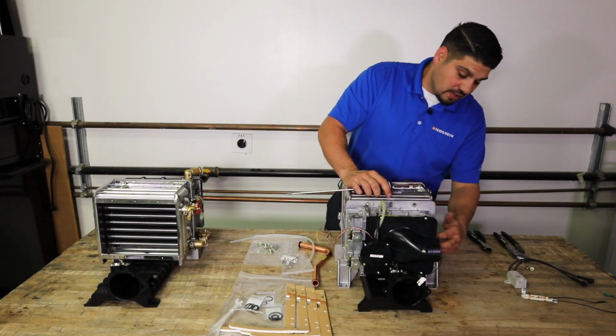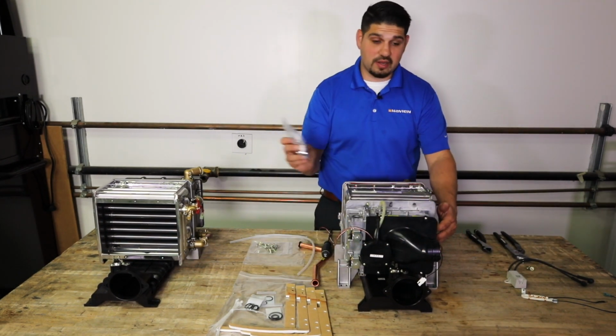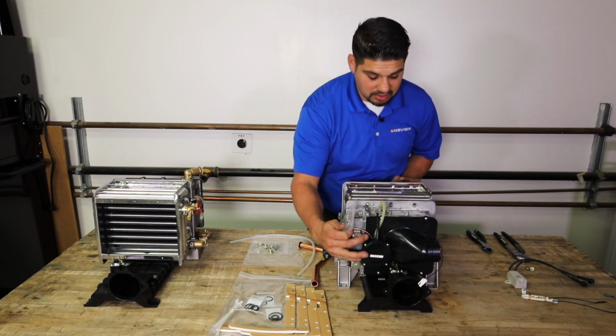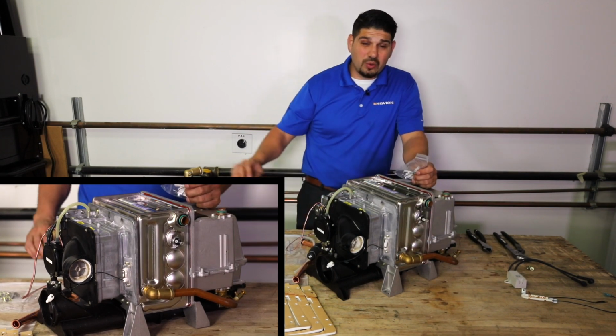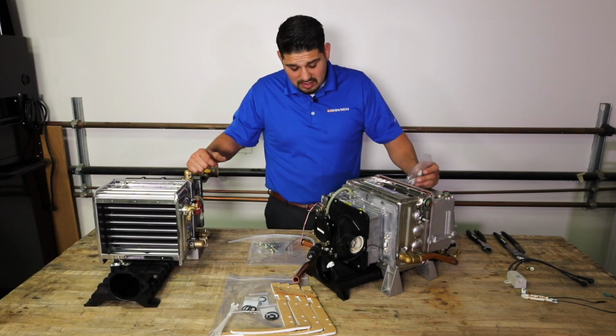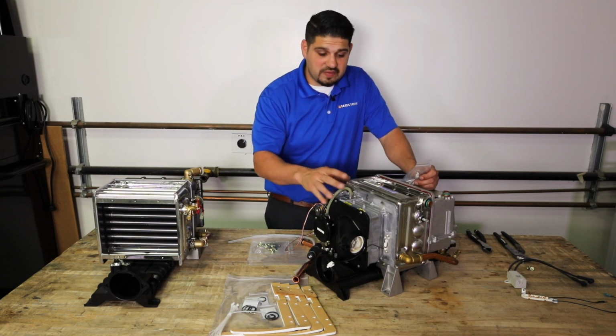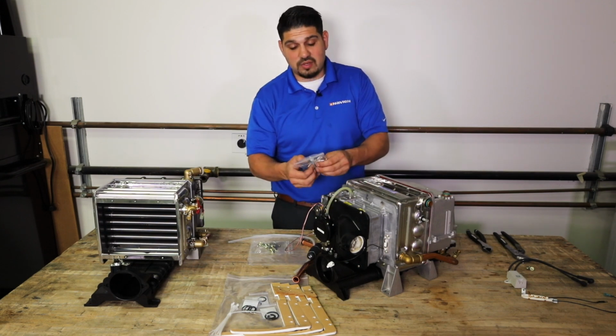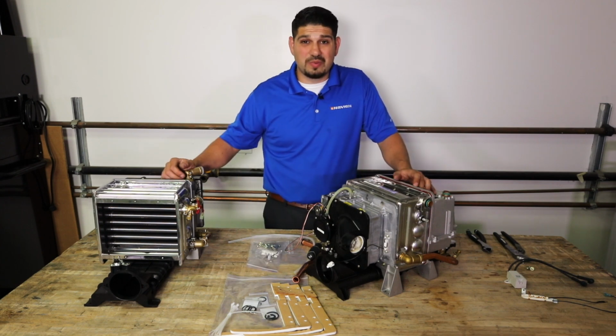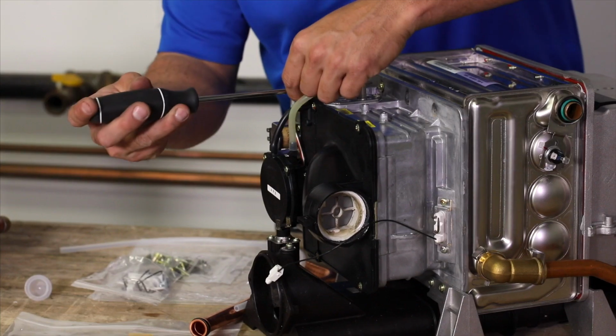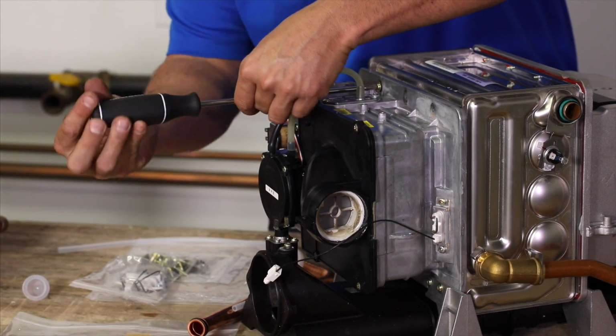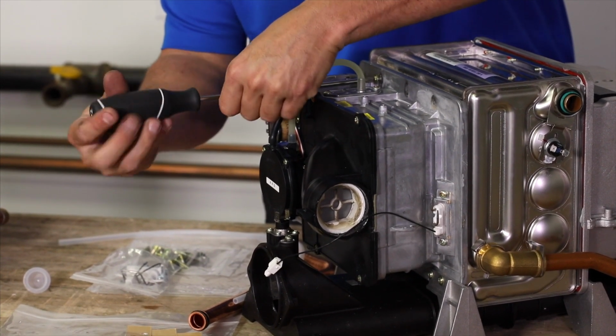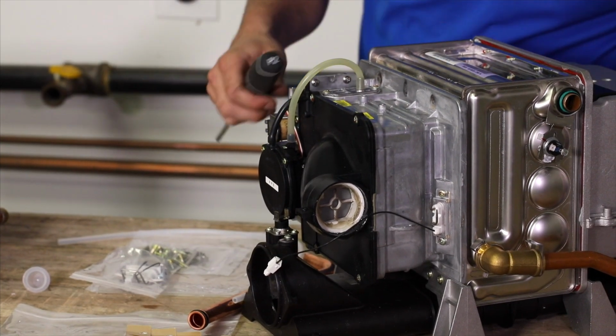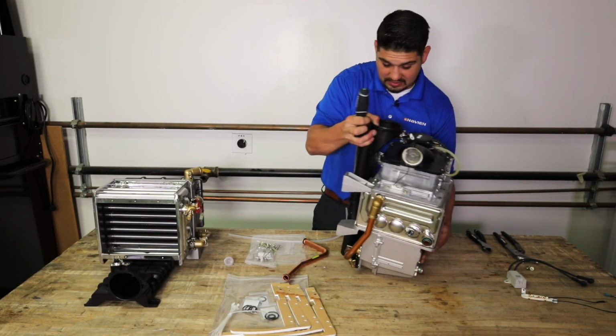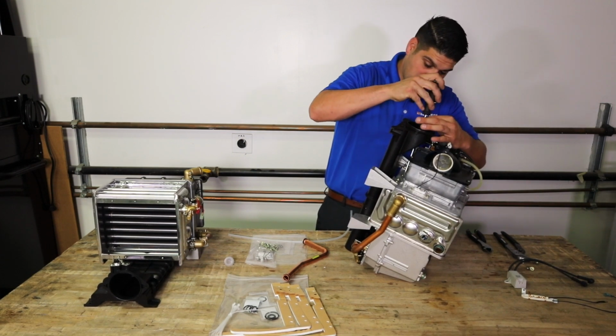Now something to remember, we do have the replacement flame rod, which goes right here, and I'll kind of swing this over so you can see the flame rod. So I would hold off on replacing the flame rod. The reason is as we're moving these over and shifting this and all that, if you bend these little bars, your spark will be cold or hot, or it won't detect flame properly. Gonna keep going here. Got the 3 screws off the front of the burner. Stand this up here so you get the 3 ones off the back.